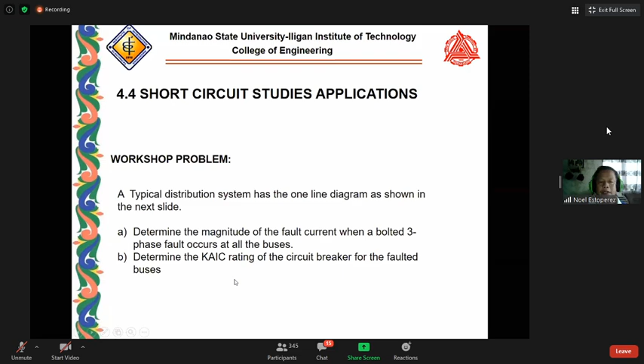So here we have a typical distribution system that has a one line diagram in the next slide. We have to determine the magnitude of the fault current when a 3-phase fault occurs at the buses. This is my basis because most of the time, if you wish to apply for the PEE, we need to solve everything. At least we know how to solve the so-called shunt faults, but we will look at the worst fault that occurs in the system, and usually this is the three-phase fault. So we then determine the rating of the circuit breaker.